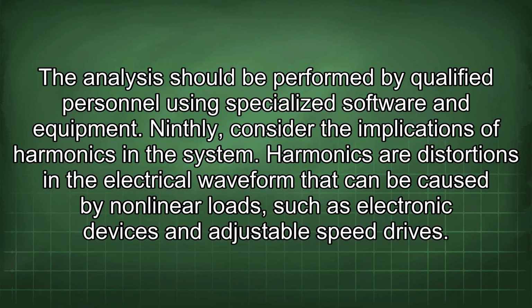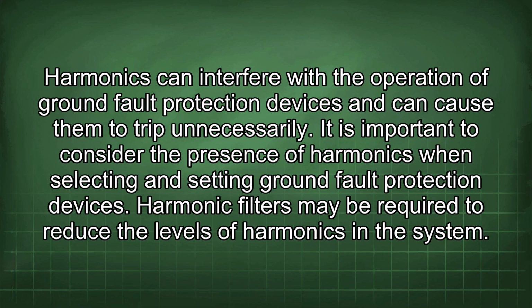Ninthly, consider the implications of harmonics in the system. Harmonics are distortions in the electrical waveform that can be caused by nonlinear loads, such as electronic devices and adjustable speed drives. Harmonics can interfere with the operation of ground fault protection devices and can cause them to trip unnecessarily. It is important to consider the presence of harmonics when selecting and setting ground fault protection devices. Harmonic filters may be required to reduce the levels of harmonics in the system.